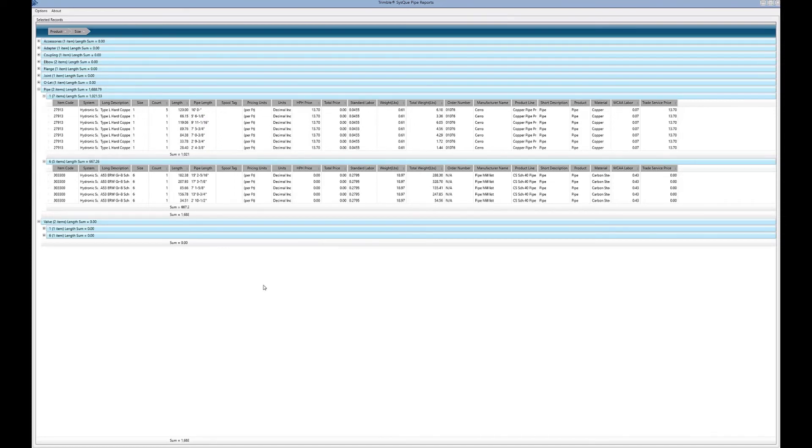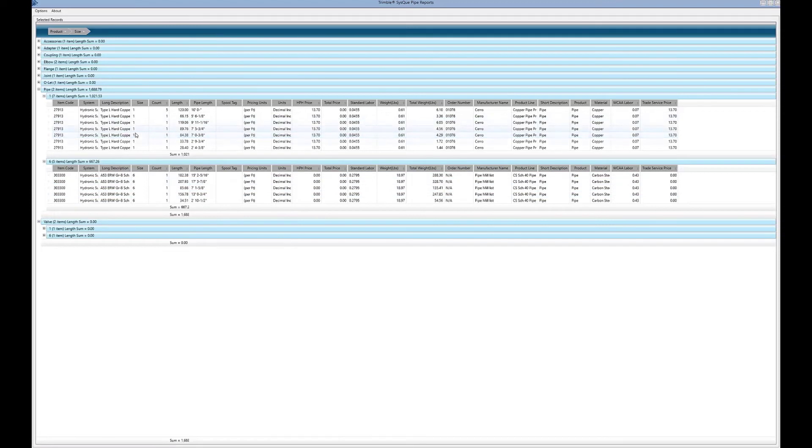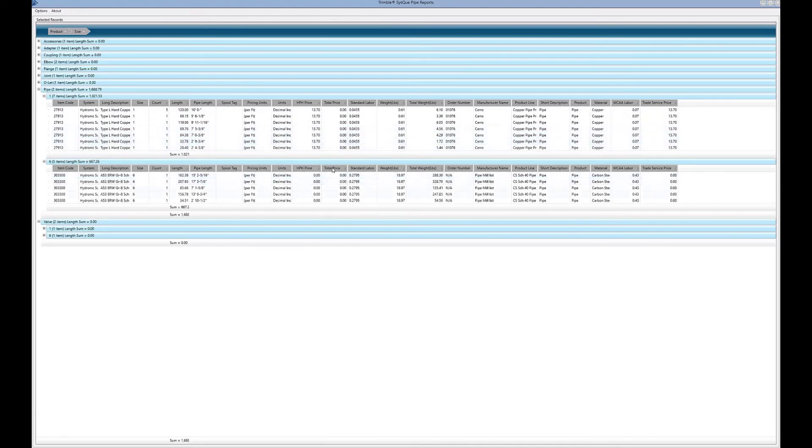The carbon steel pipe is coming from what's called a pipe mill list - that is generic carbon steel pipe A53 etc., but because it's not allocated to a region, you'll discover you got zero pricing on there. The copper has pricing because it's coming from Zurn and they've got pricing in there. For the steel pipe, if you want to get the local pricing, you can allocate price or change your pipes from the pipe mill list standard to your specific region.